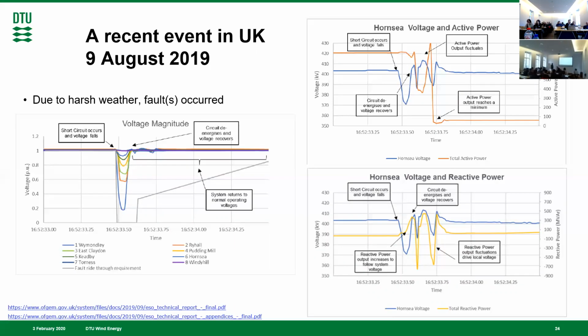At one of those points was the Hornsea offshore wind farm. I won't dwell too much on the graph, but the point is that while it initially behaved as expected under a fault-ride-through condition, for whatever reason, probably a lack of proper coordination between the different control levels, from the wind turbines all the way to the STATCOM installed onshore, it started having oscillations of reactive power. At some point, the wind turbines, being very sensitive to high currents, shut down to protect themselves and avoid burning the power electronics.